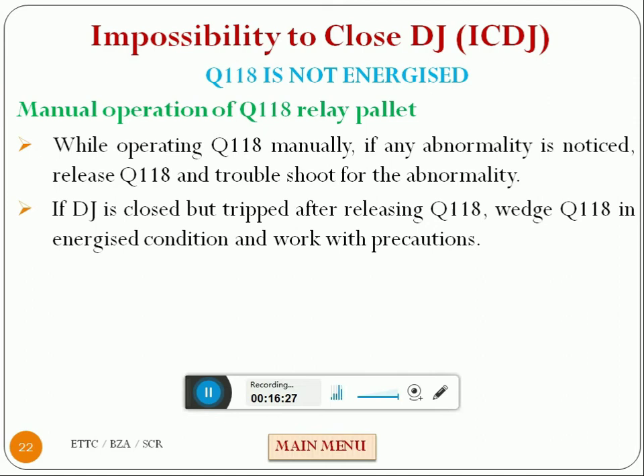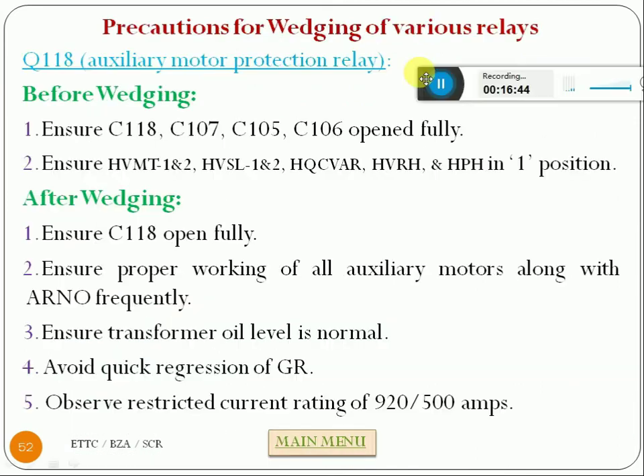If manual operation is not successful, wedge Q118 in energized condition. Before wedging, ensure C118, C105, 106, 107 are fully open, and the switch positions on the Q118 branch are in normal position, one position. After wedging, ensure C118 is fully open. Ensure proper working of auxiliary motors along with the Arno on the Q118 branch. Check the transformer oil level frequently, and quick regression is to be avoided. We have to follow current readings 920 by 500 amps. This is the troubleshooting for Q118 not energizing.